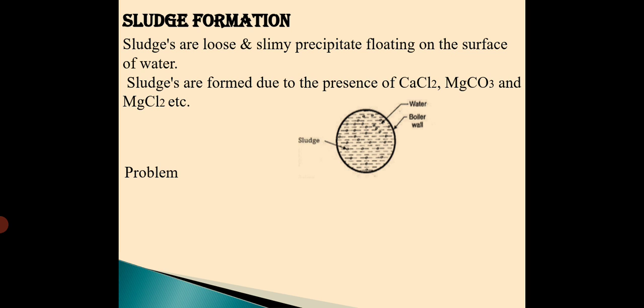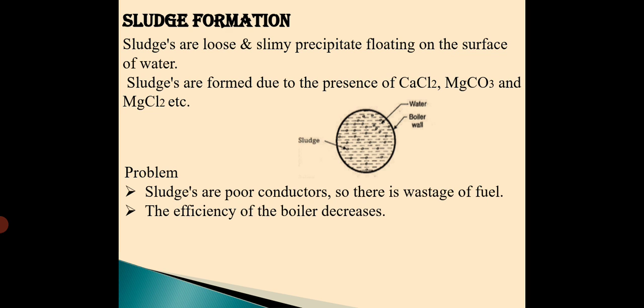What are the problems? The same problems like scaling - they reduce the efficiency of the boiler and also these sludges are poor conductors, so there is wastage of fuel. How to overcome this problem? The solution is you have to directly use soft water or we have to go for frequent blow down operation. What is frequent blow down operation? It is nothing but the removal of the salt concentrated water by opening the valve.